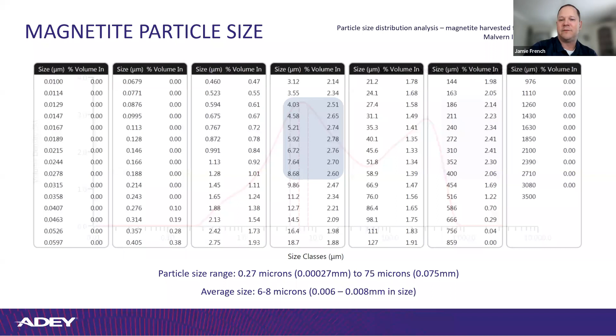Here's a leading dirt separator's chart that I pulled off, I'm not going to say who it is, but the parameters for the testing are on the right, and you can see they do several passes. We're guessing they used a silica sand and not magnetite for this test. Once you get to between 60 and 30 microns, the performance really drops off, and we're talking less than that, 30 down to 6 to 8 microns, the typical size of magnetite.